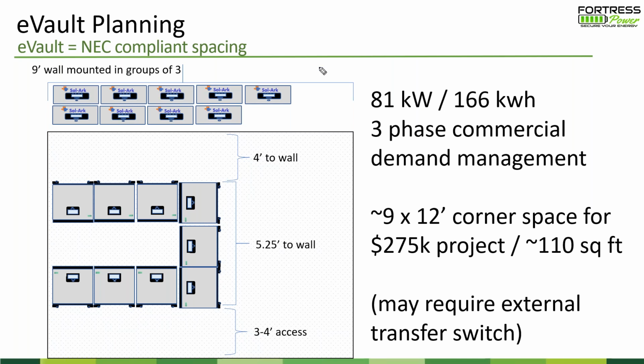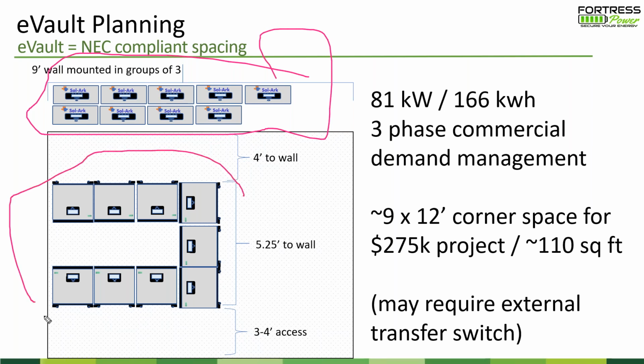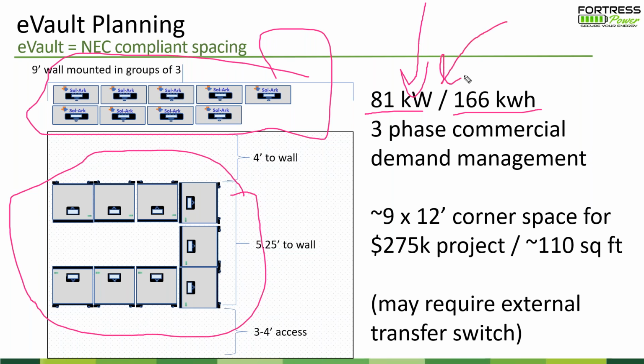But if you look at a project with 9 Sol-Arks and 9 Fortress E-Vaults, that gives you about 81 kW of DC coupled demand management capability on about 166 kilowatt hours of storage. So you could demand manage 80 kW off of the commercial facility's peak load.